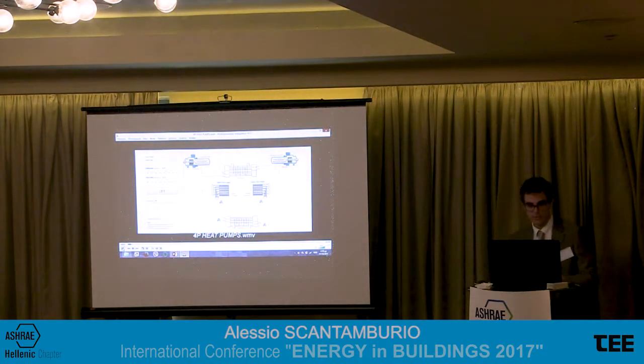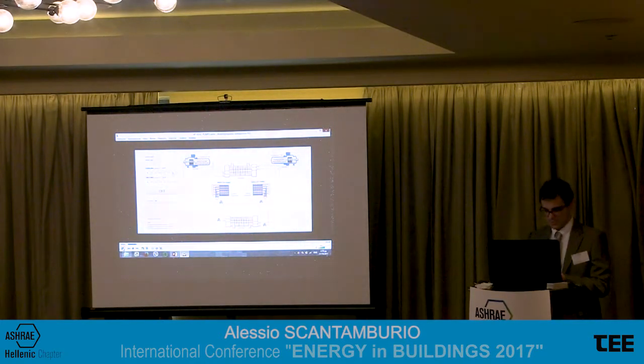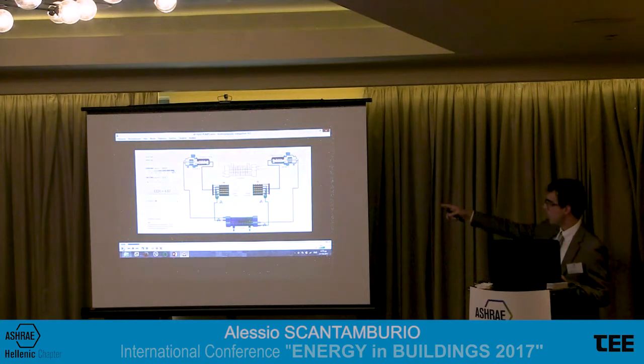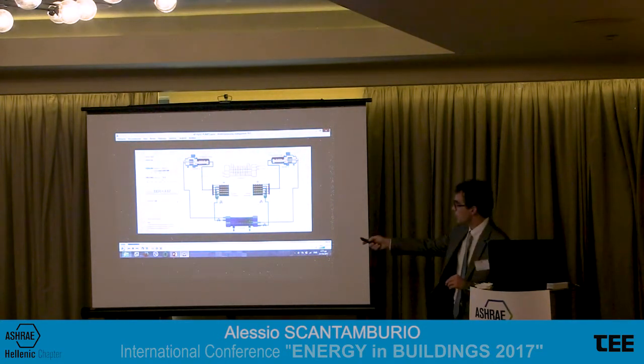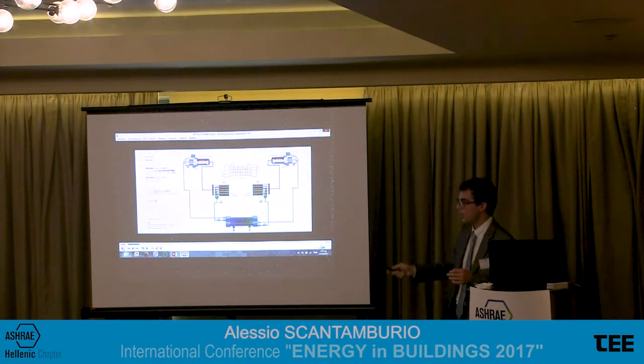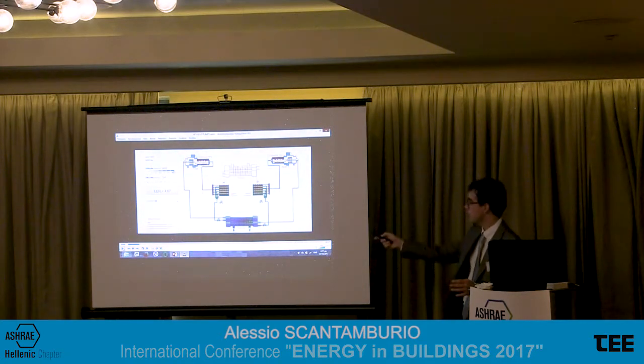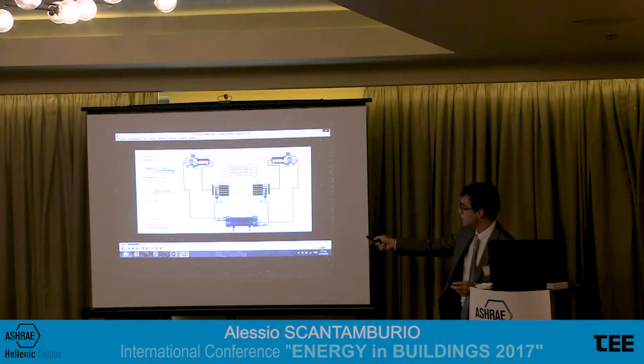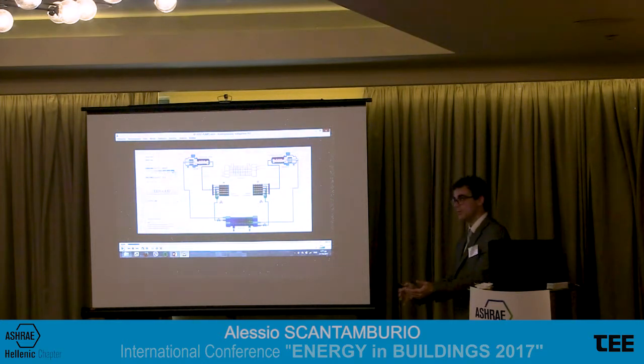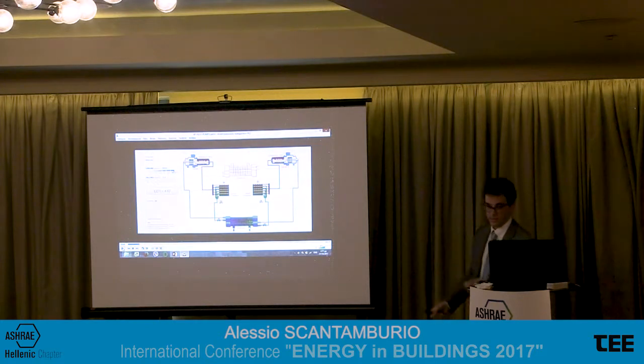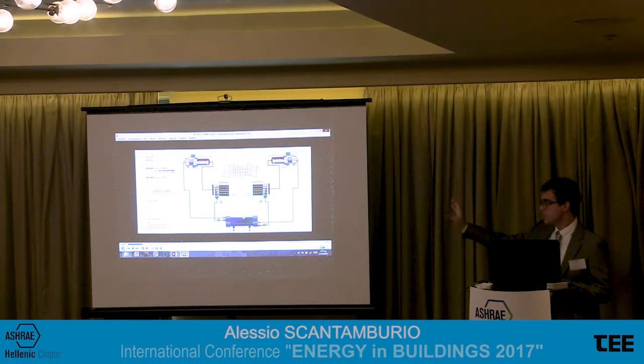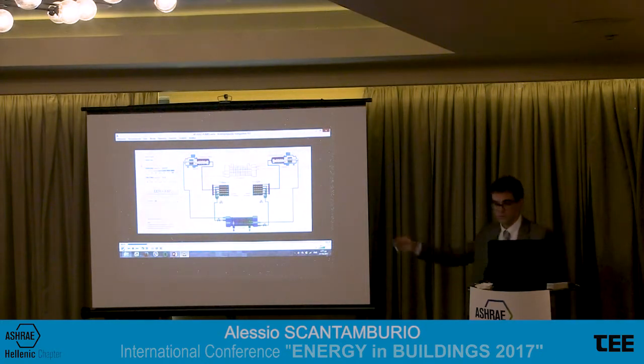So this is the same refrigerant circuit, okay? For example, if the building is requiring 100% of cooling capacity, like in this case, the building in this condition is requiring only cooling capacity, total capacity. This means that both circuits, here we have two circuits, both compressors are running at their maximum capacity, using the evaporator to evaporate all the refrigerant flow. And then, as we are not requiring any hot water at the condenser side, the auxiliary exchanger is used as a condenser to get rid of the heat I am removing at the evaporator. In this case, the function is like a standard chiller. In this case, an air-to-water chiller.